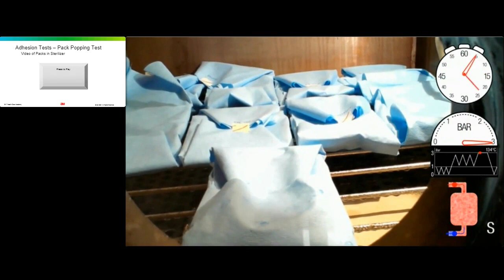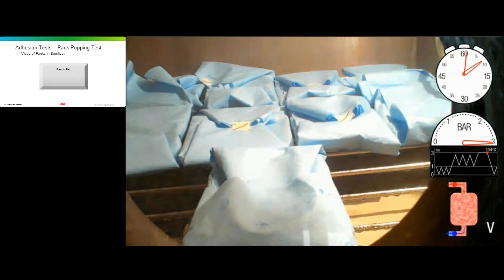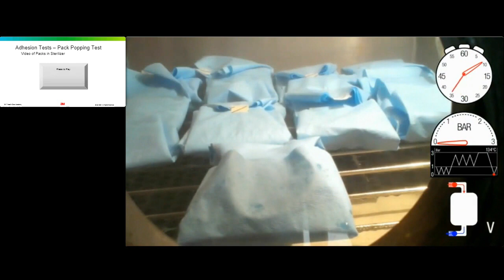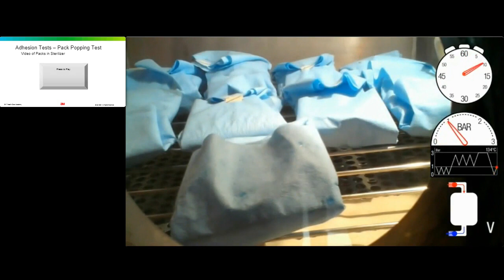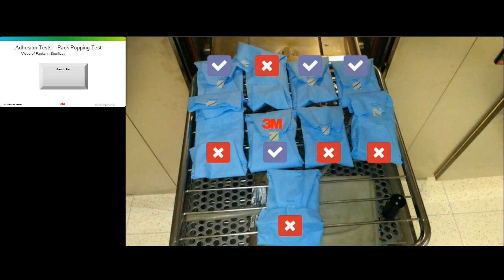We're now going into the actual sterilization phase. So inside the chamber is relatively quiescent. We're now at 134 degrees at about 3 bar absolute pressure in a steam environment. And you can see that we've speeded this section up by virtue of the fact the clock's zooming around. We're now going into the drying phase, so we're dropping the pressure inside the chamber, and you can see that as that pressure falls, the packs begin to balloon as a result of the condensate inside them flashing off, and it obviously takes time for the steam to permeate through the wrapping material. So you can see in this graphic the tapes which were able to hold that force in that wrapping material in place, and then those which were not able to.